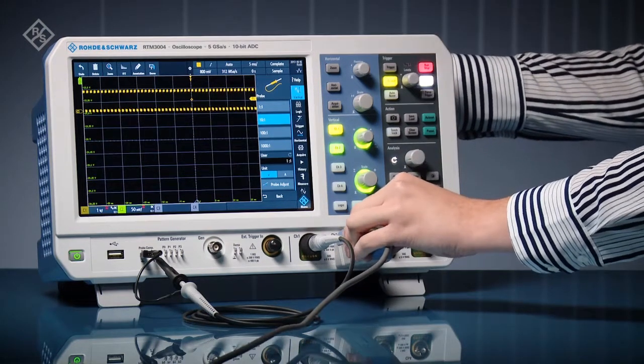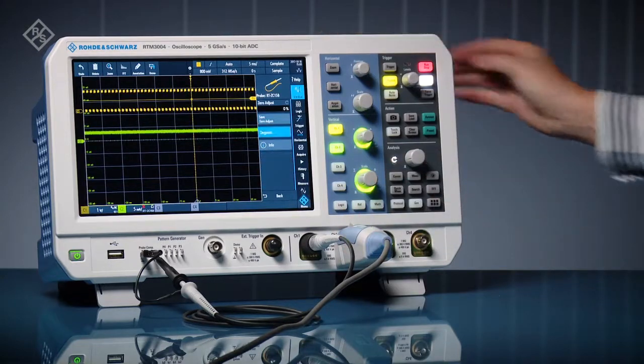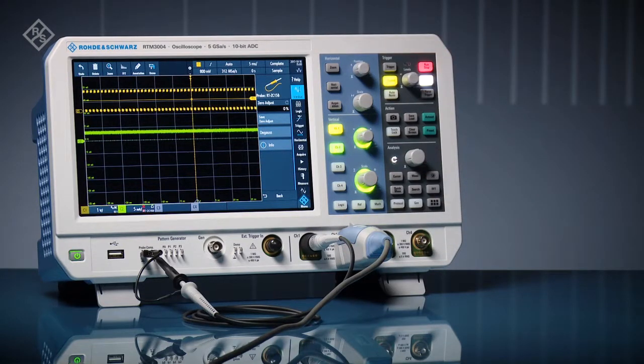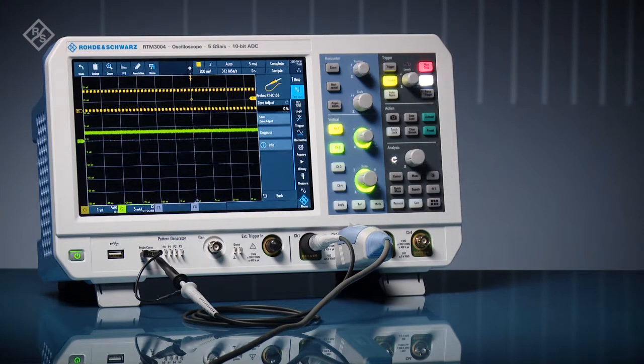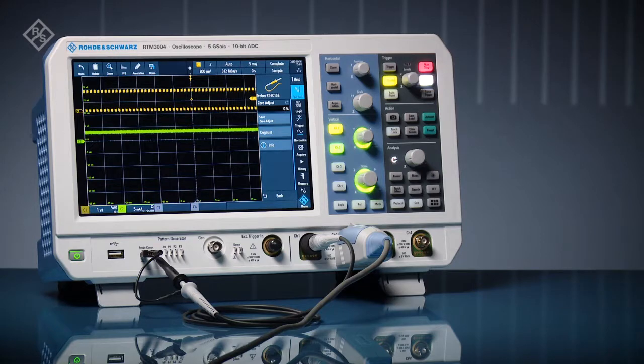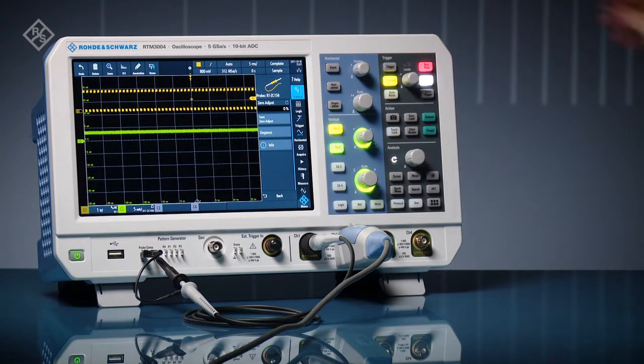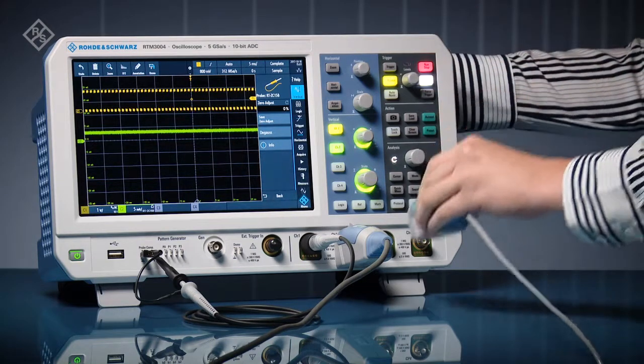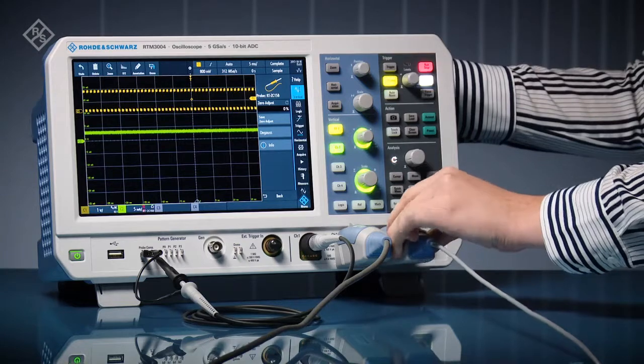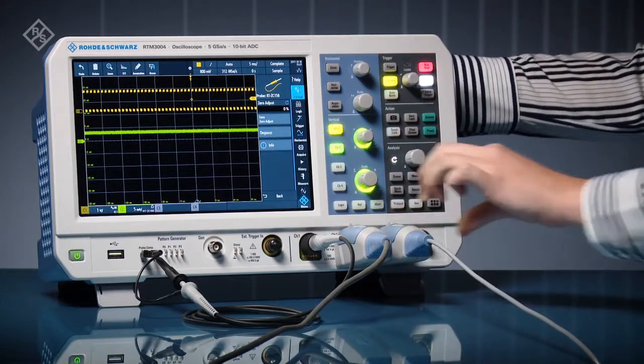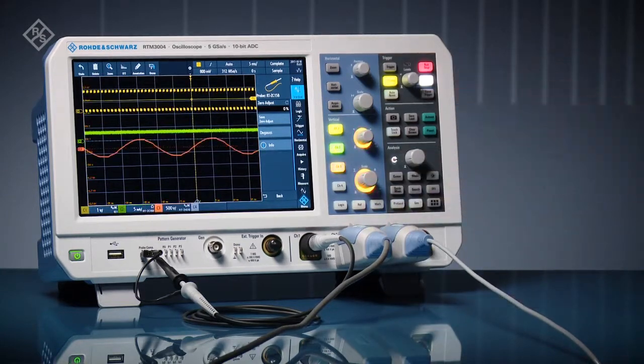The oscilloscope automatically detects the probe and sets up the scope, like showing vertical scaling in amps. Choose from a wide range of voltage probes. The scope knows if it's single-ended.